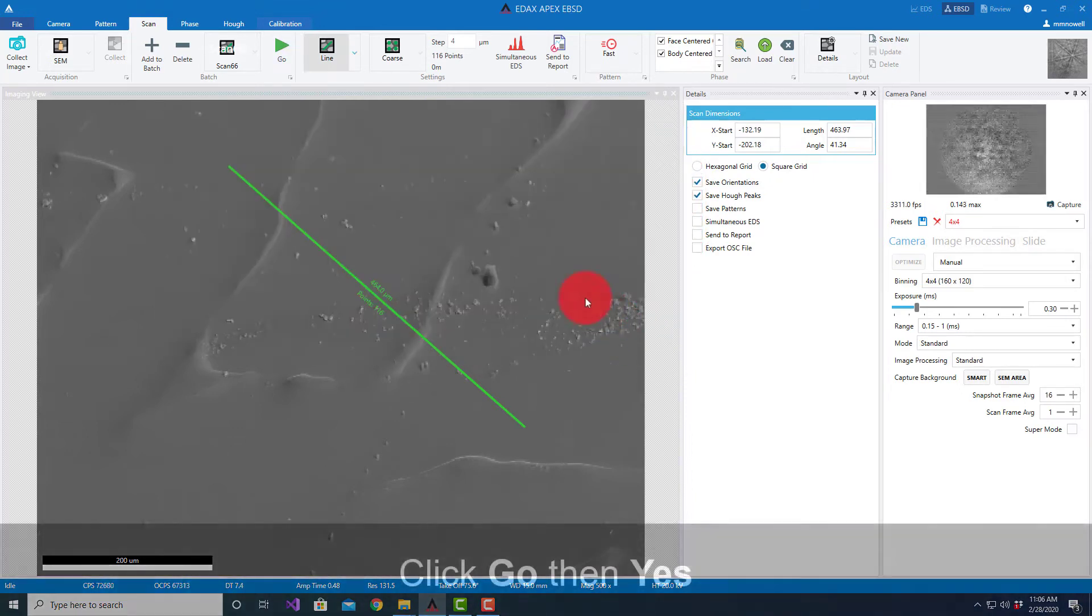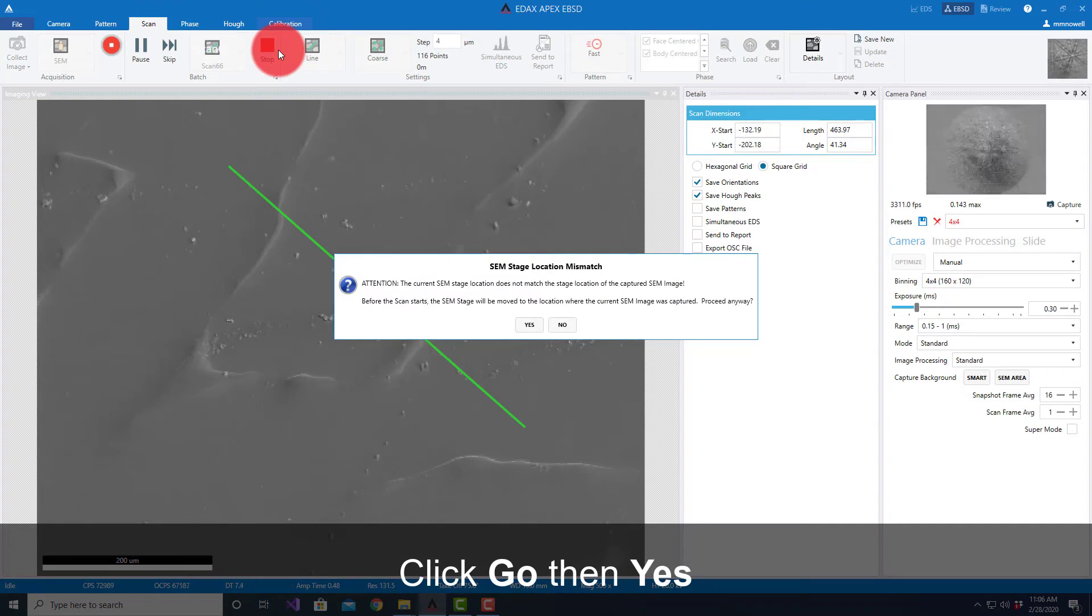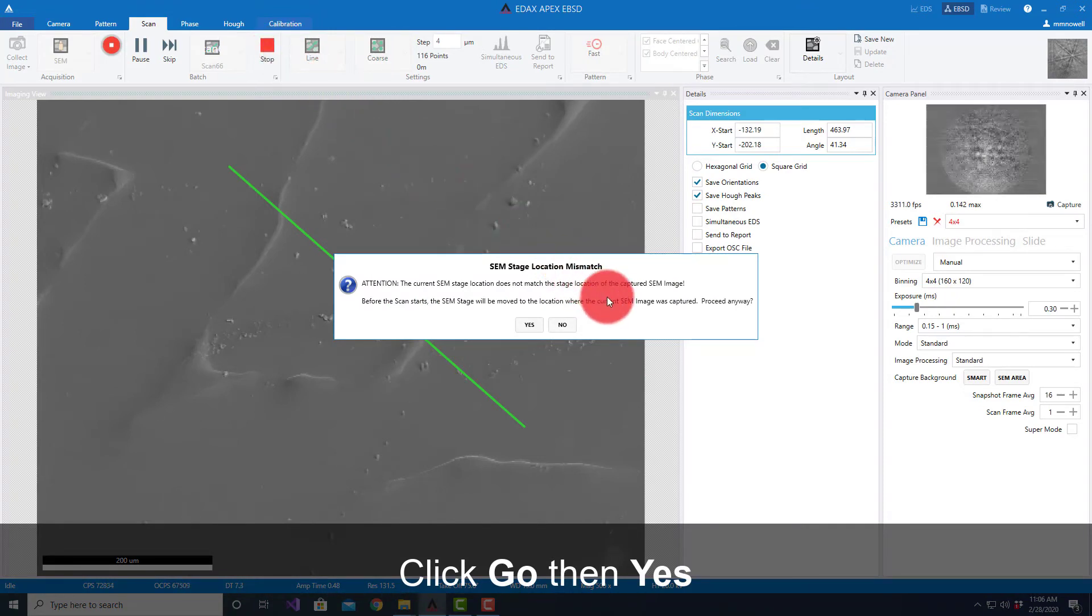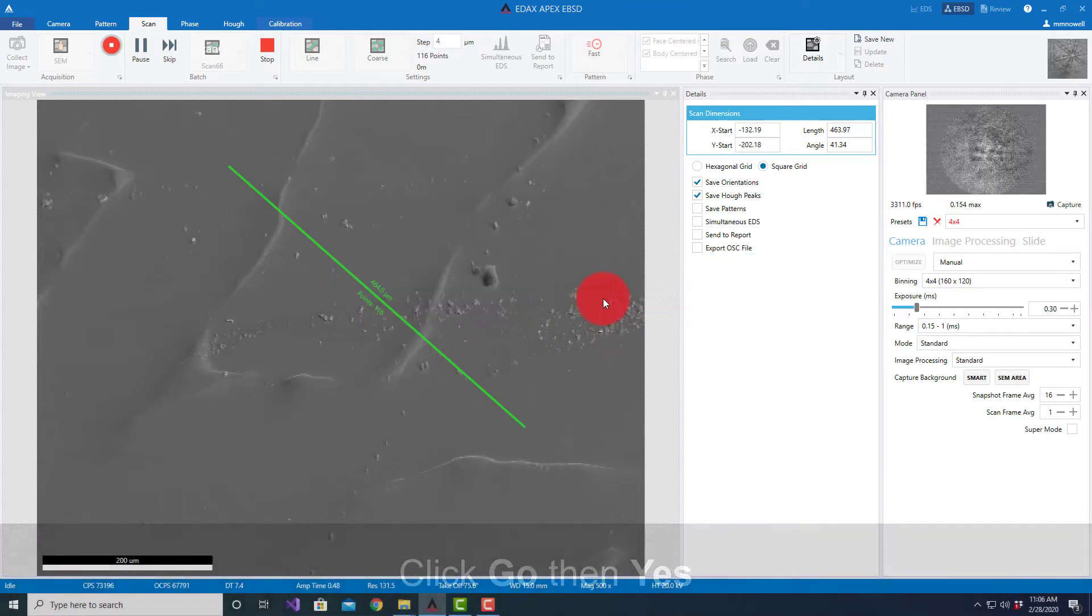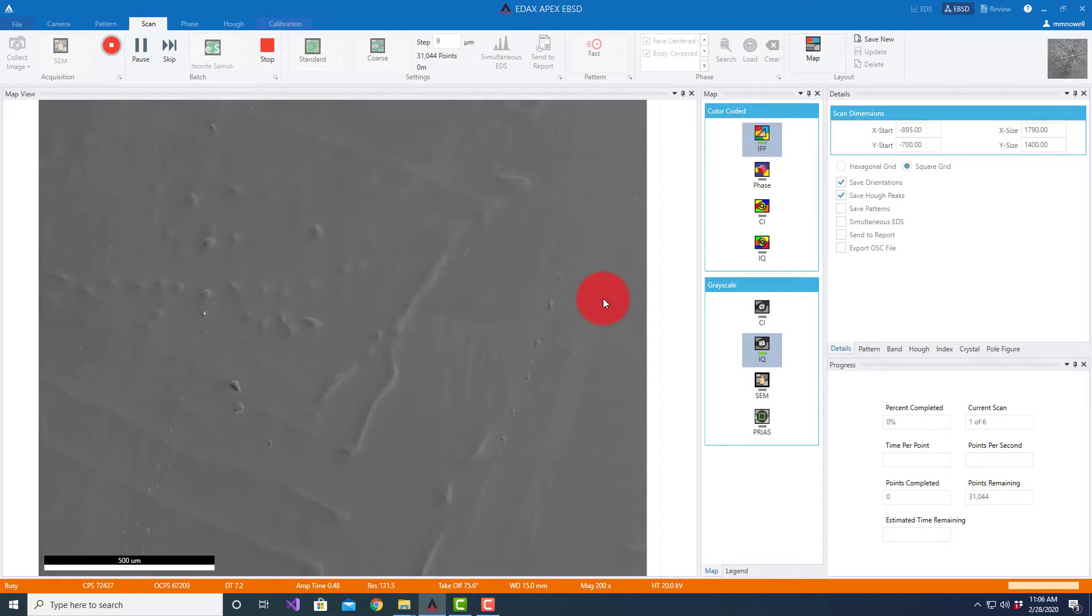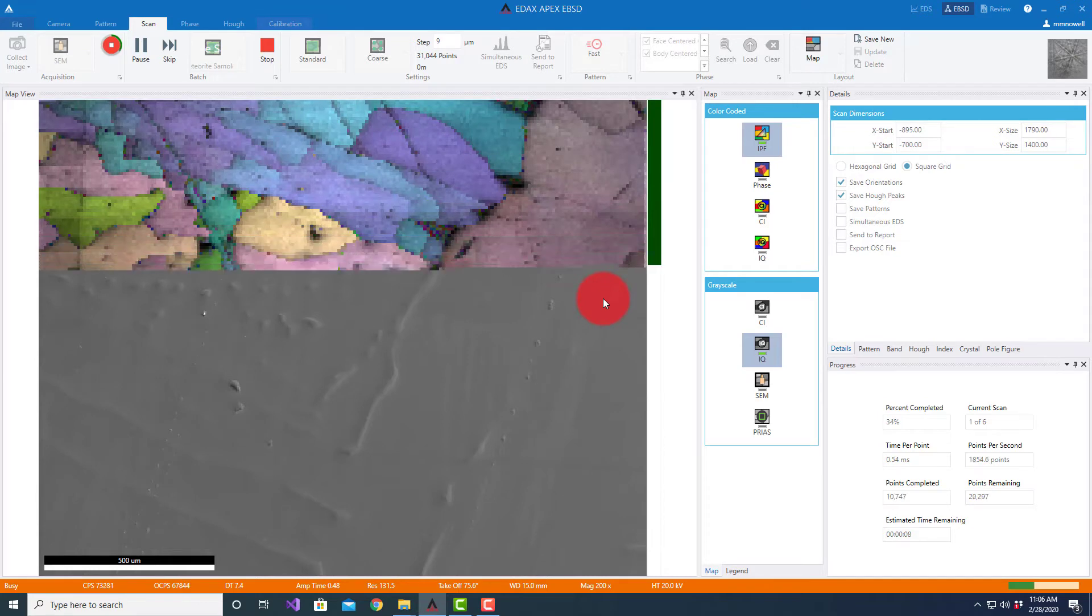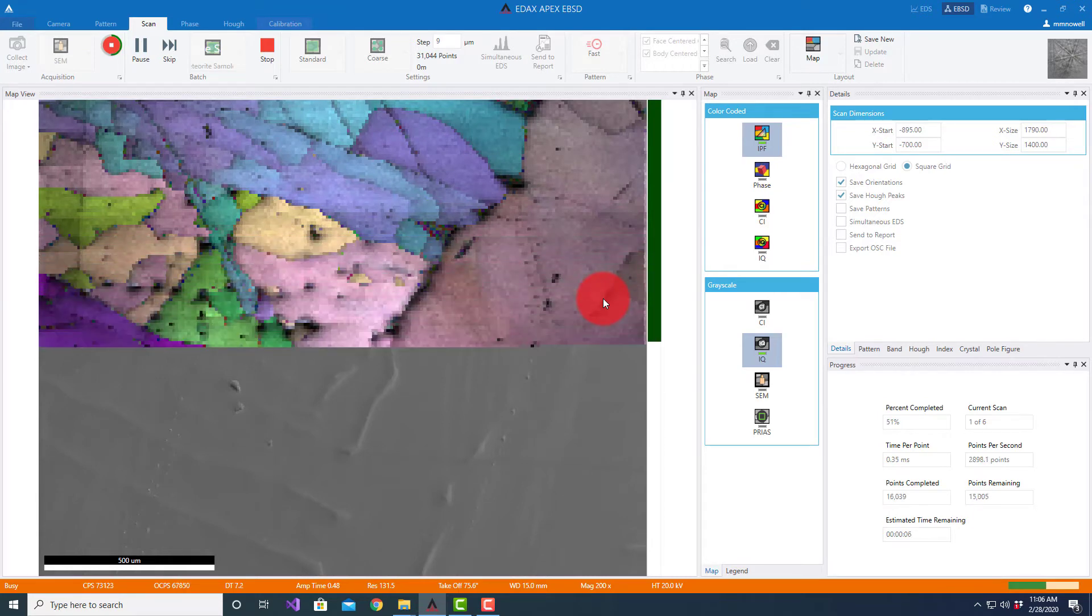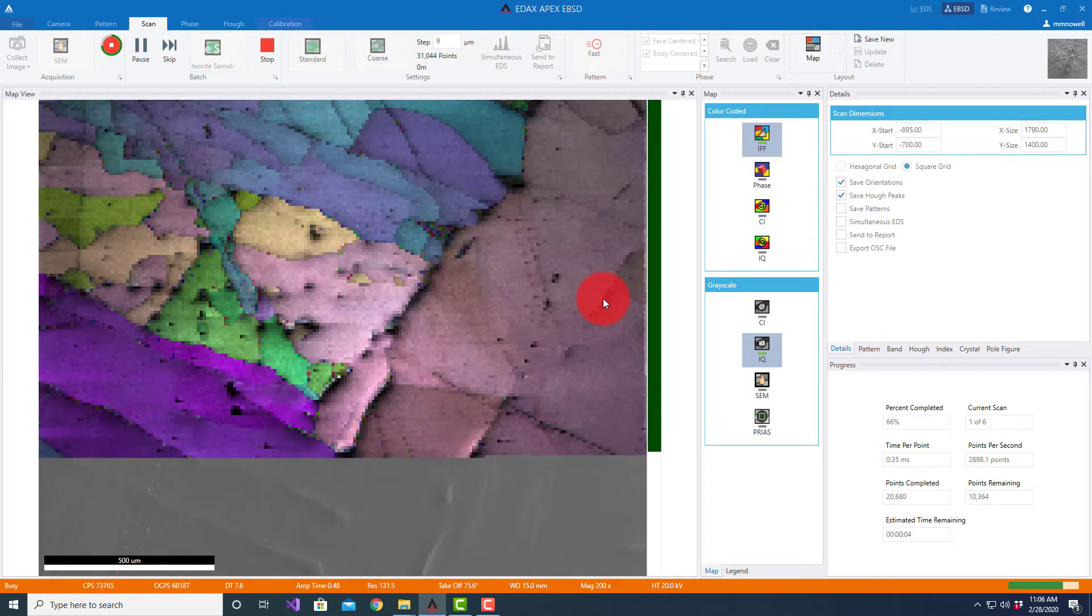I can now just hit Go. Because we're going to move the stage, it's going to give me a little warning to let you know things are going to move. I want to go ahead and say yes, let's move to that position. It's going to run a quick scan, just going to go through the set here. The scans themselves should be pretty quick with the velocity setup for about 2,500 points a second, and doing a coarse scan they'll be pretty quick scans.